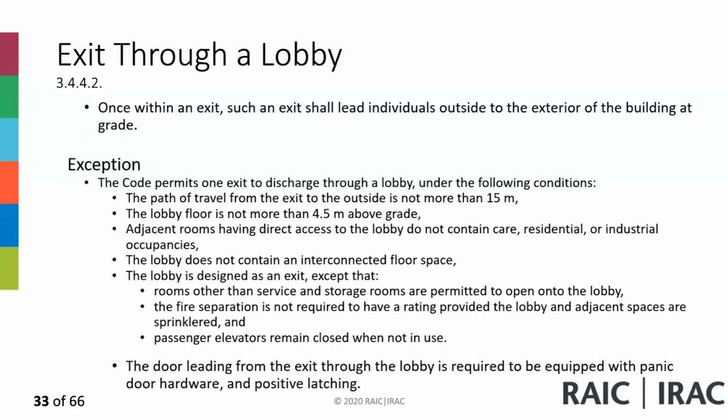So we know the exception of 3.2.6.2(6). It's allowed under certain conditions: a sprinklered lobby area, and it's only for certain types of occupancies. The lobby conforms to the requirement for exits, so it needs to be fire separated, except that rooms other than service rooms and storage rooms are permitted to open directly to the lobby.